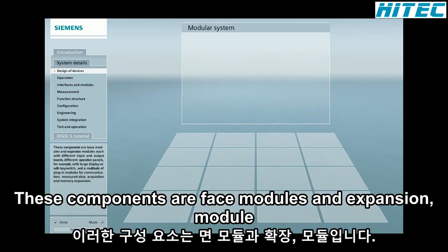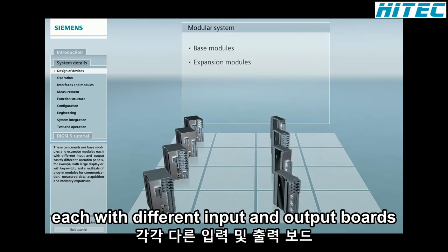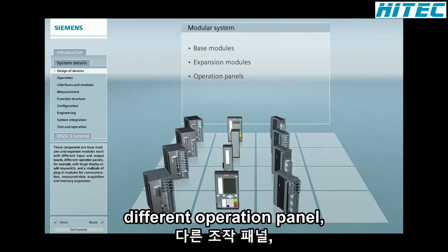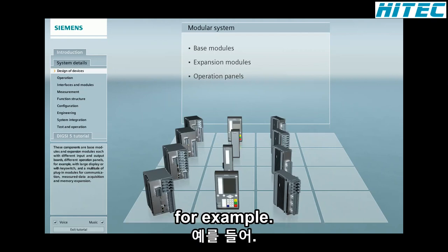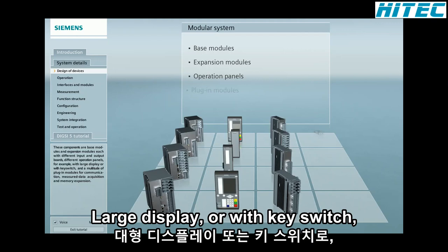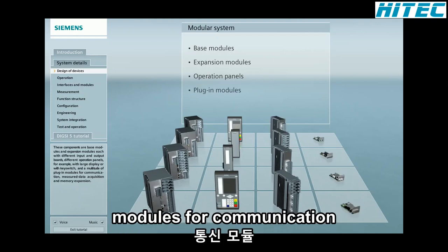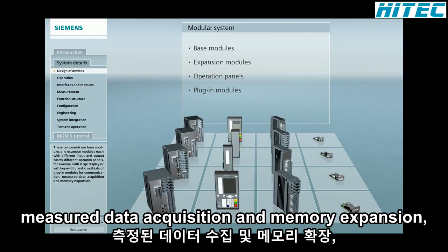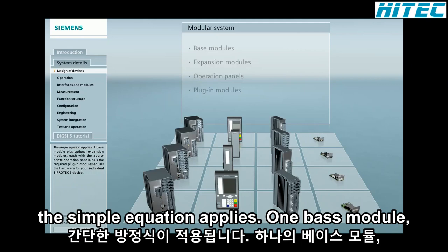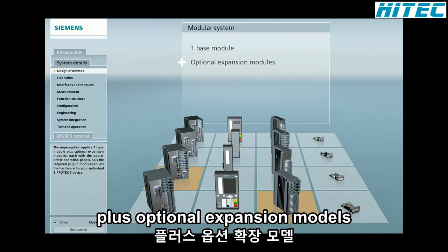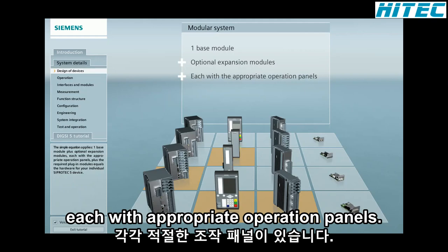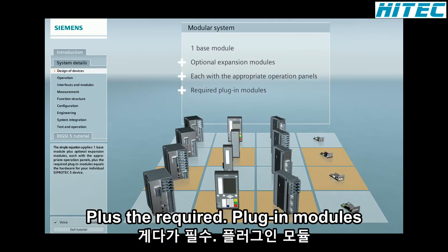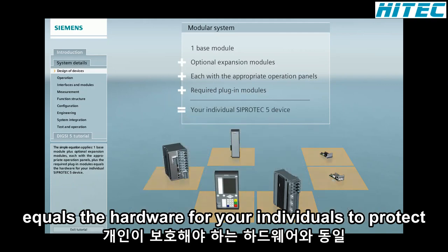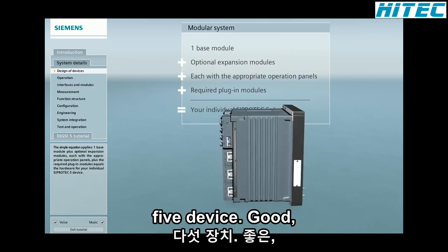These components are base modules and expansion modules, each with different input and output boards, different operation panels, for example with large display or with key switch, and a multitude of plug-in modules for communication, measured data acquisition, and memory expansion. The simple equation applies: one base module plus optional expansion modules, each with the appropriate operation panels, plus the required plug-in modules equals the hardware for your individual SIPROTEC 5 device.